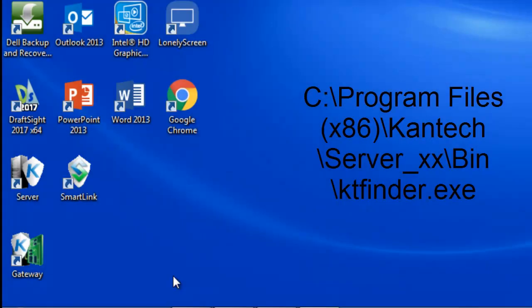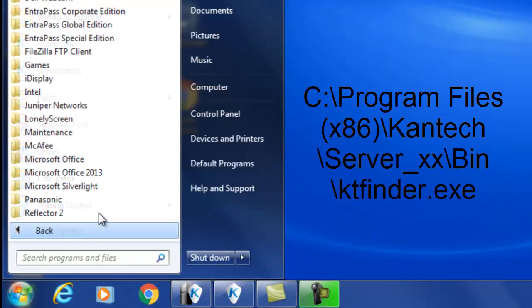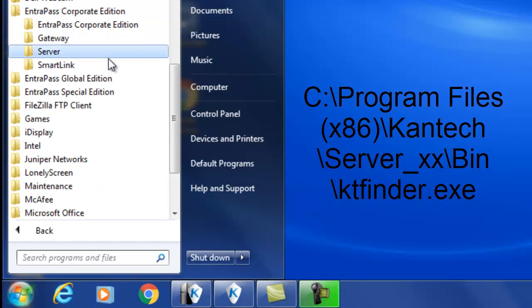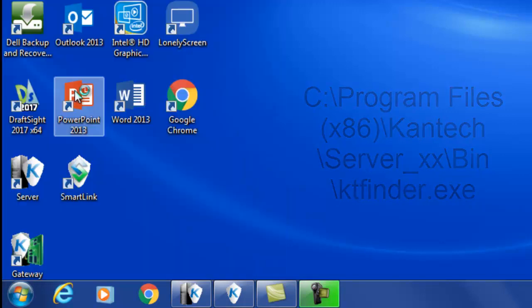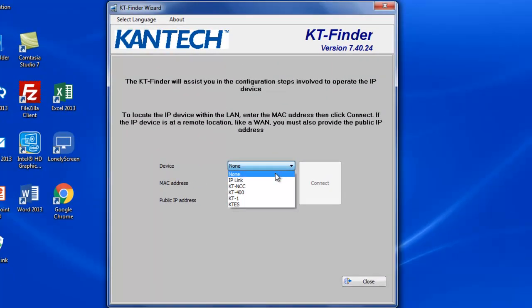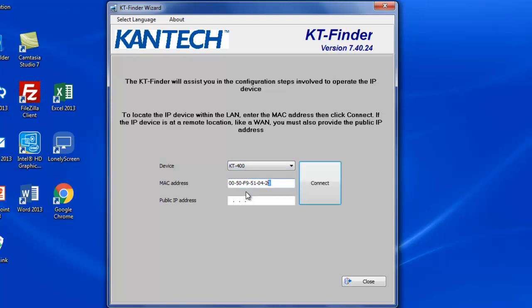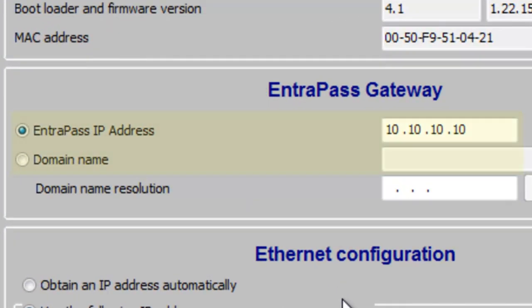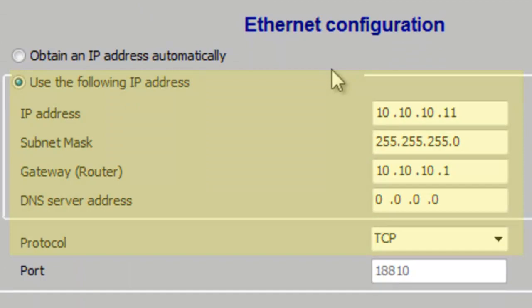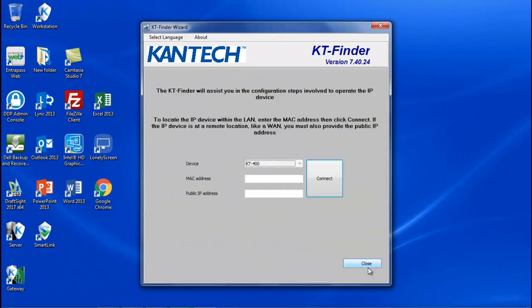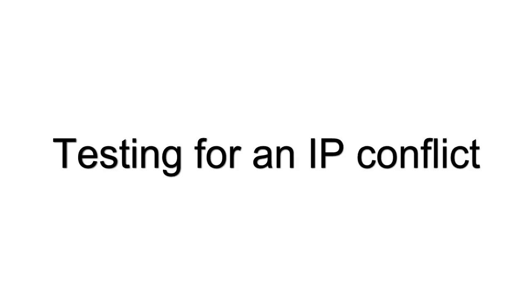You can use KTFinder to validate the information inside the controller. Stop your gateway and start the KTFinder program. Select your device and enter the MAC address. Here you will see your EntraPass gateway and the controller information. If the controller has already communicated, you won't be able to change any information. You may have to default the controller.